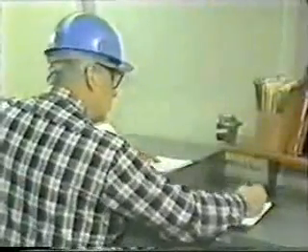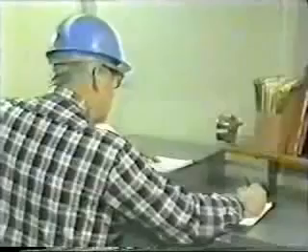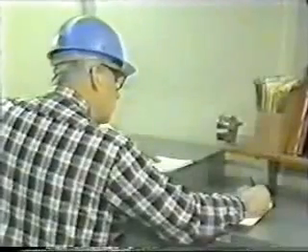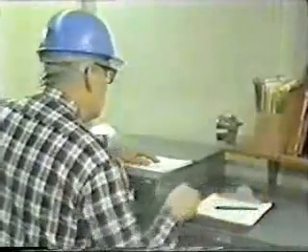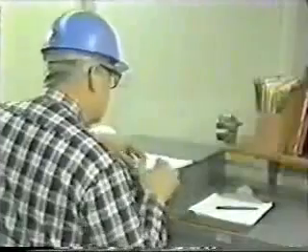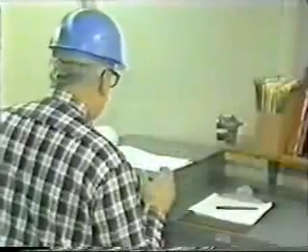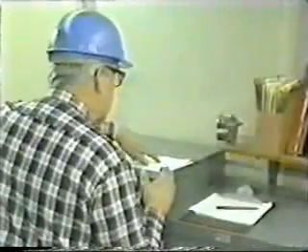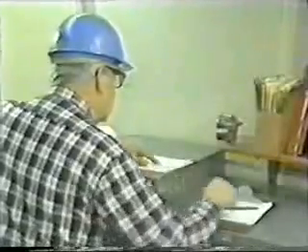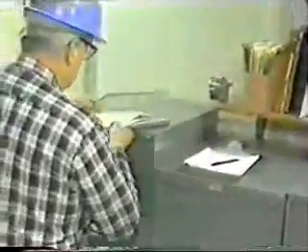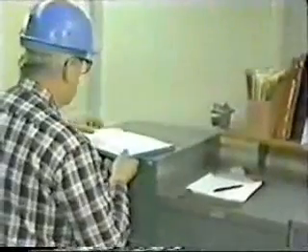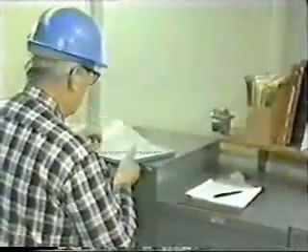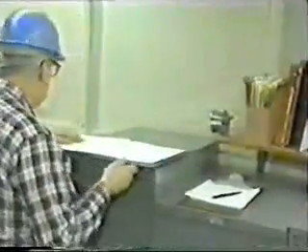So Gene takes a look at the logs first. The logs note that the bearings were recently greased while the pump was out of service. They also note when the pump was started up again. The logs indicate who greased the bearings, so Gene makes a mental note to talk with him. The maintenance logs show the recent greasing of the bearings and mention the type of grease required. No other work has been performed for many months on this pump.